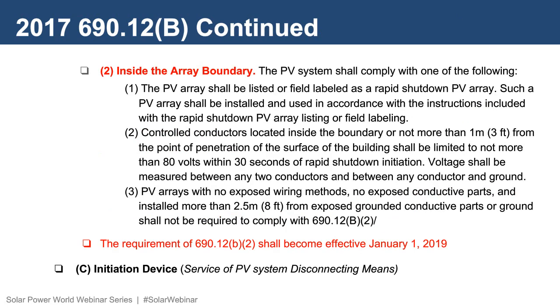Controlled conductors within the array boundary must comply with one of 3 options. First option is the PV array must be listed or field labeled as a rapid shutdown array. The second option, controlled conductors within the array boundary must be limited to 80 volts or less within 30 seconds. The third option, which allows for building integrated PV arrays, states that no exposed wiring methods and no exposed conductive parts could be installed, and they must all be installed outside of 8 feet from exposed grounded conductive parts. If it meets this third option, then you do not have to comply with the second option.